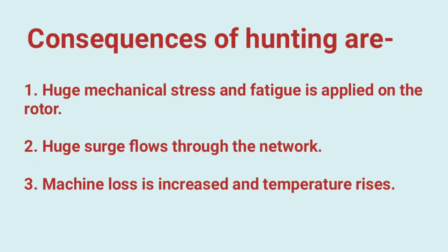Now let's know about some consequences of hunting. 1. Huge mechanical stress and fatigue is applied on the rotor. 2. Huge surge flows through the network. 3. Machine loss is increased and temperature rises.